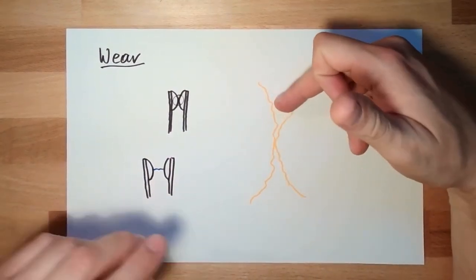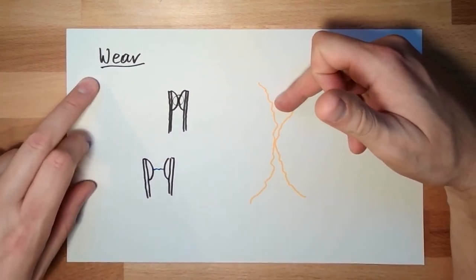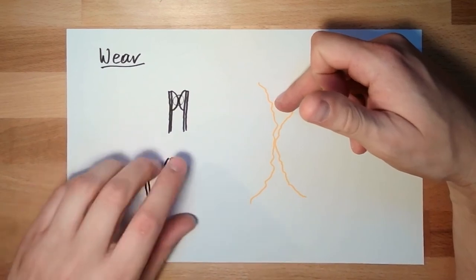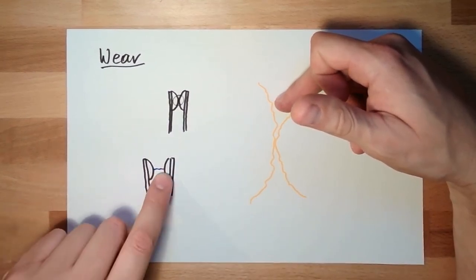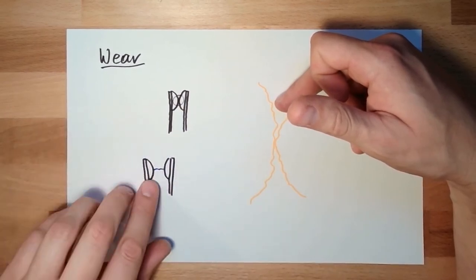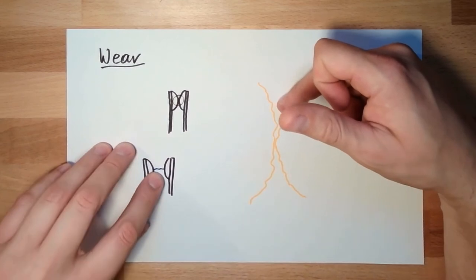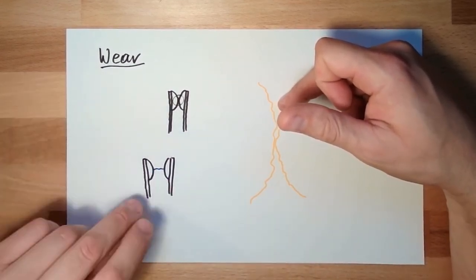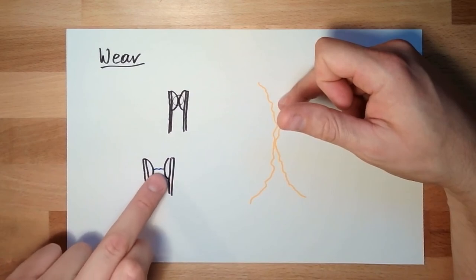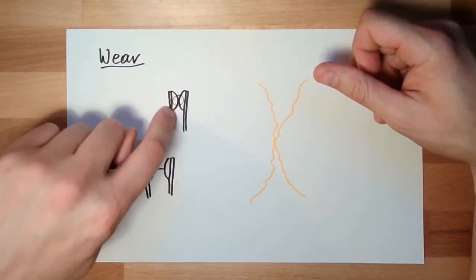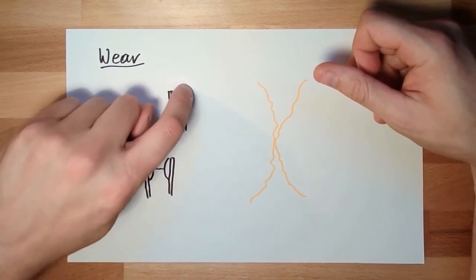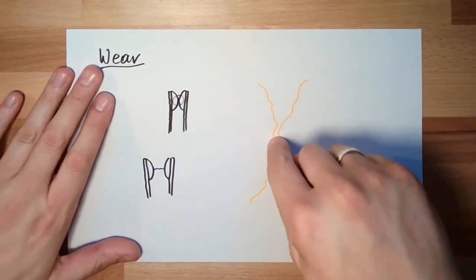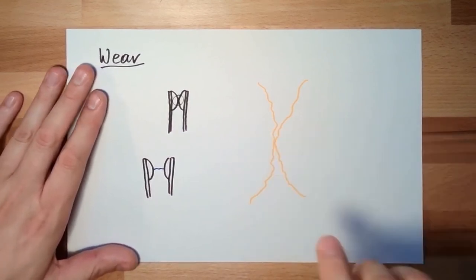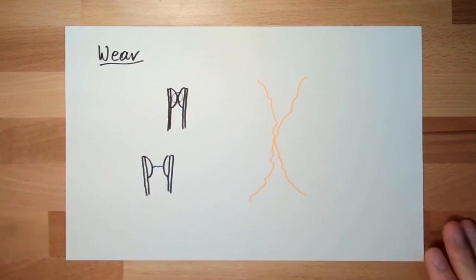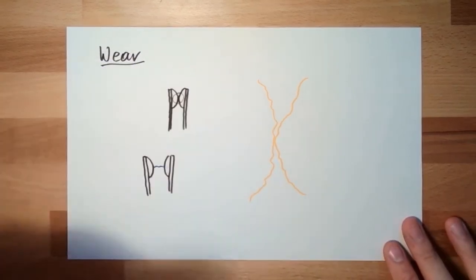So this is why a mechanical contact has wear, especially if you switch inductive loads. Then this is extreme. Then this flash spark will last quite a while. If we have to switch inductive loads, we have to switch either small loads or take additional measures to prevent this spark. In the end, it might happen that the surface of this formerly very flawless round contact is looking like this. Then it's wear. Who cares? Until the thing is melted down, it takes ages.